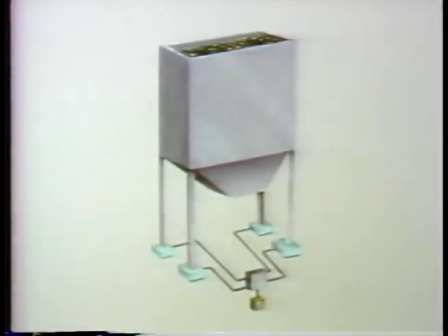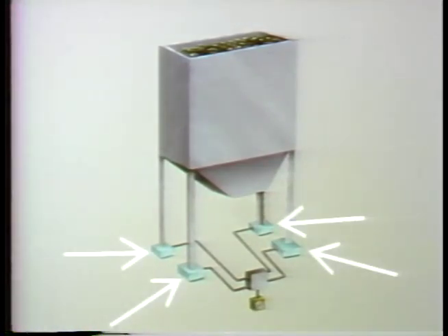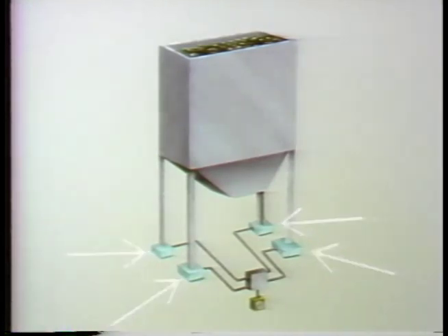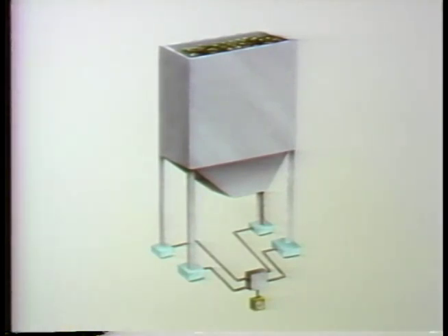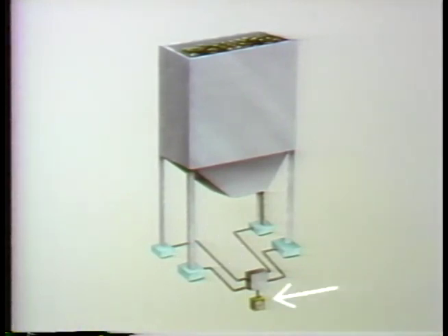Here's a simplified diagram showing how load cells are used. Here is a bin containing coal, and here are four load cells. A load cell is nothing more than a sophisticated scale that measures weight. They're installed so that they measure the weight of the bin and its contents. The weight on all four cells is added together by a summing device, which calculates a level measurement and displays it on an indicator.